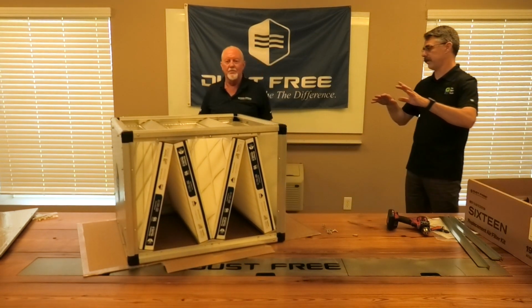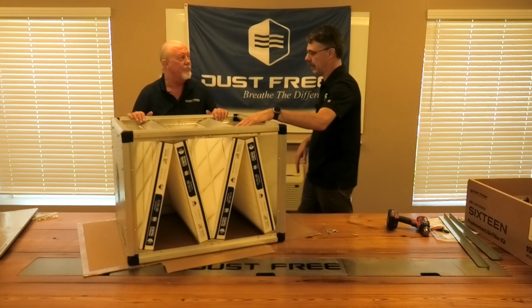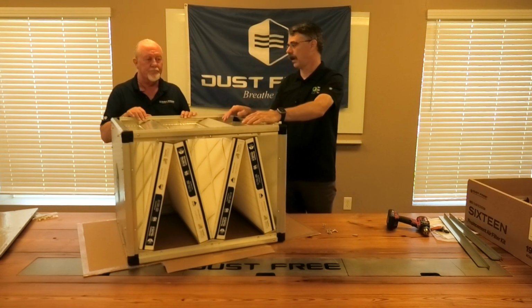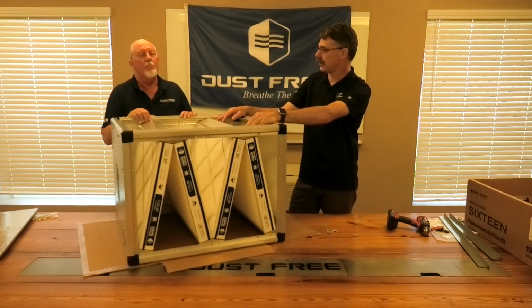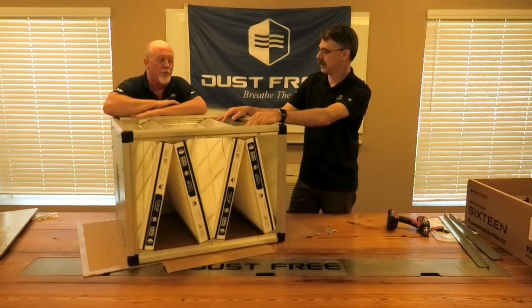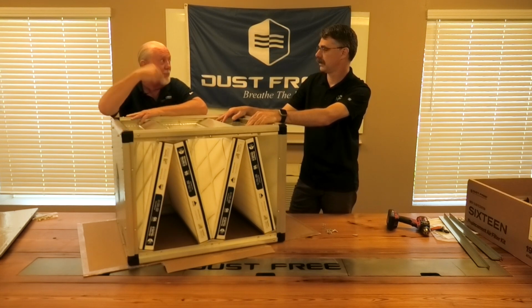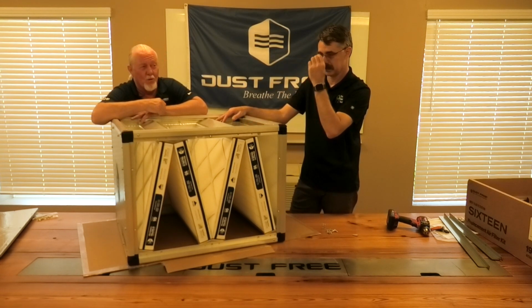This is for the 5-ton, or 2,000 CFM of air, and we're talking about a 0.18 static pressure drop. When you get down to the 4-ton, which is 1,600 CFM, that static drop is dropping. We're at a 0.13.